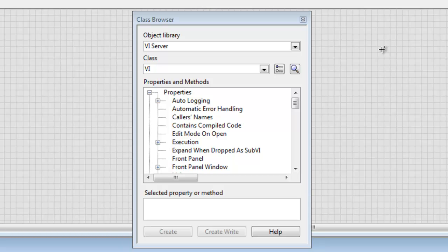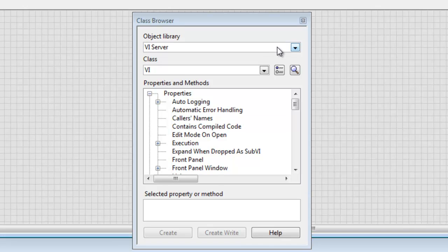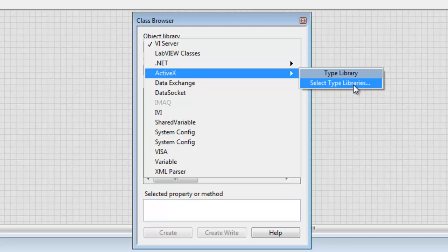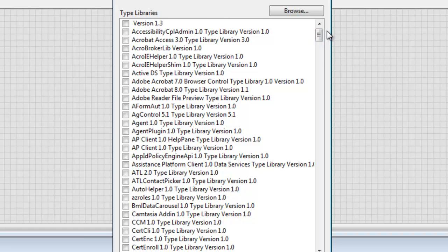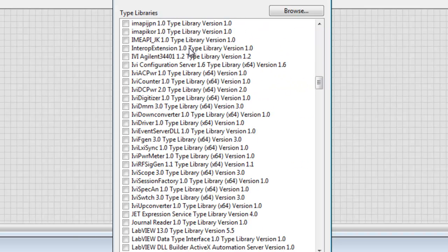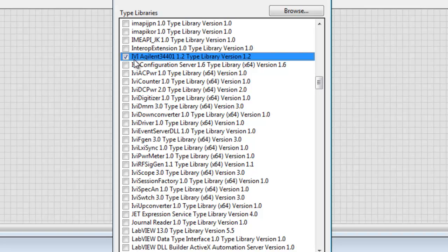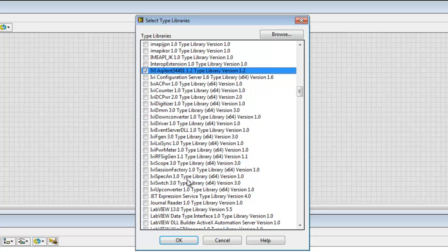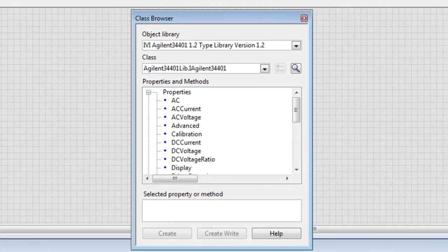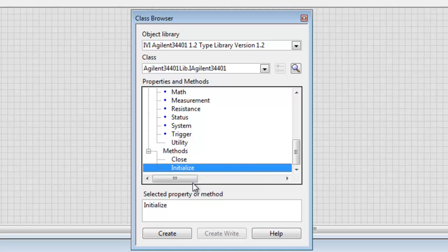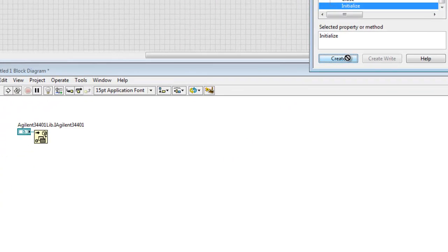class browser. From the Object Library dropdown, select ActiveX, and then choose Select Type Libraries. From the options available, you're going to want to choose the IVI Agilent 34401 1.2 Type Library version 1.2, and then click OK. Now the class browser is set to the correct object, and you should see methods and properties for the Agilent IVI-COM driver.